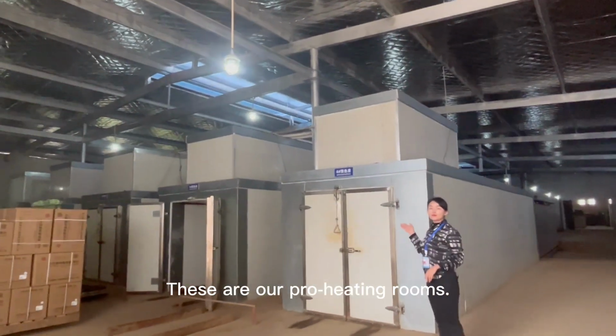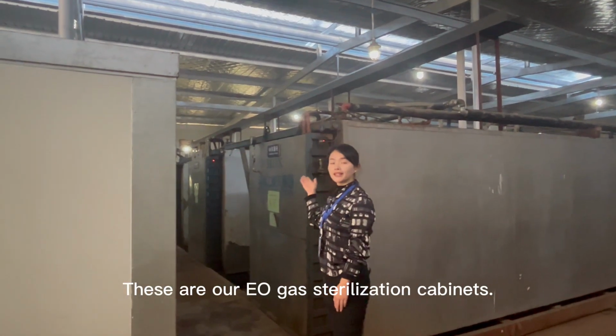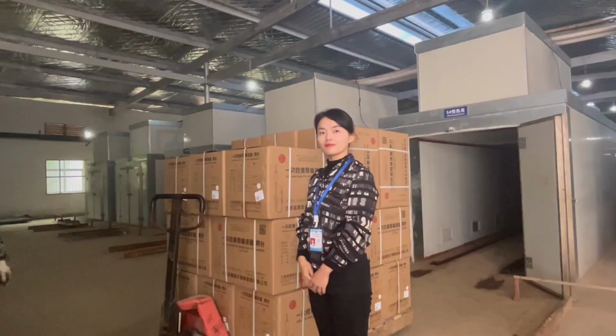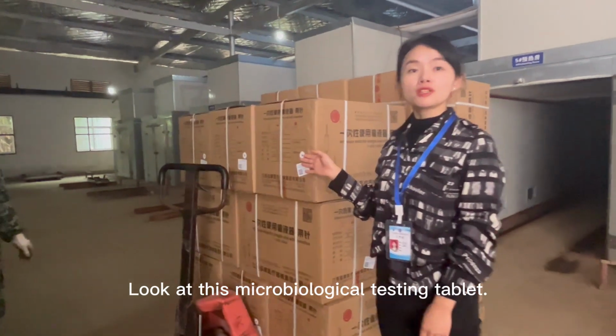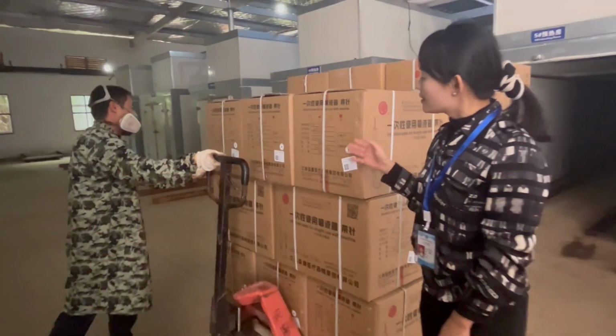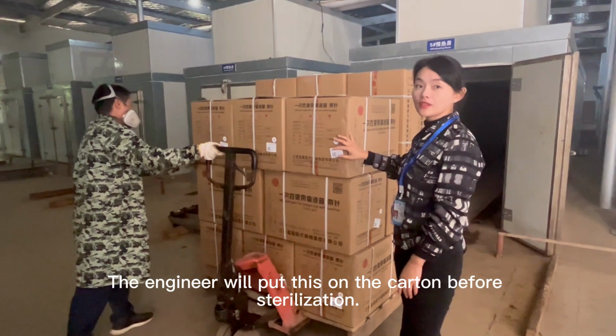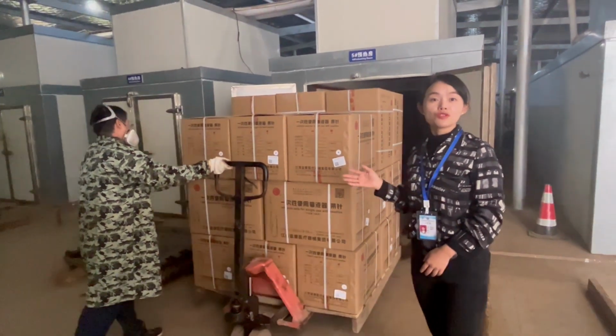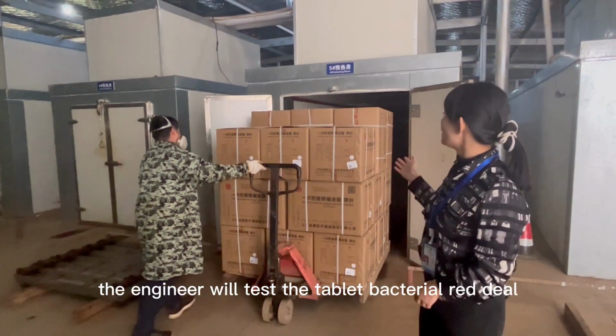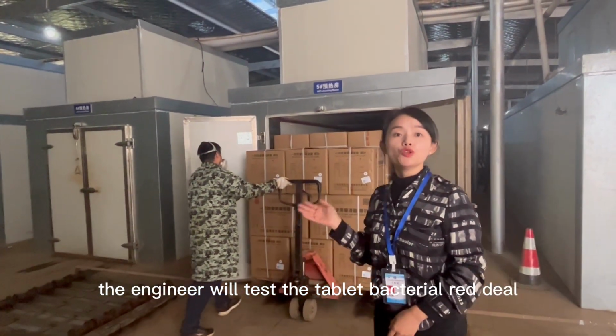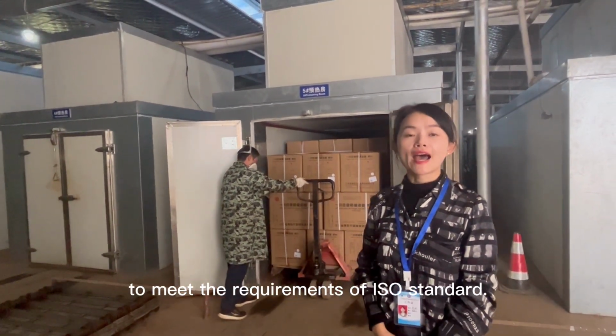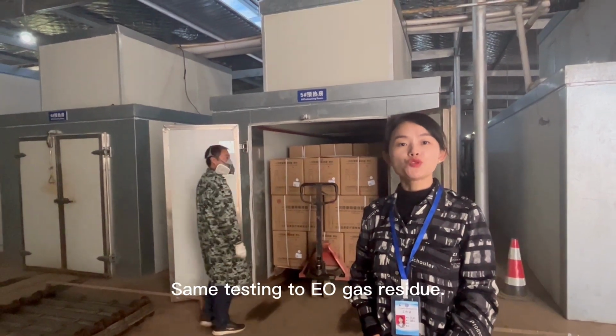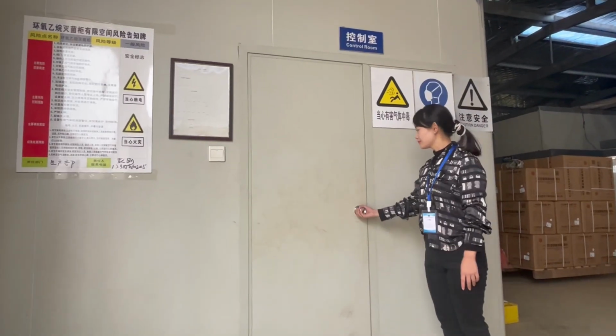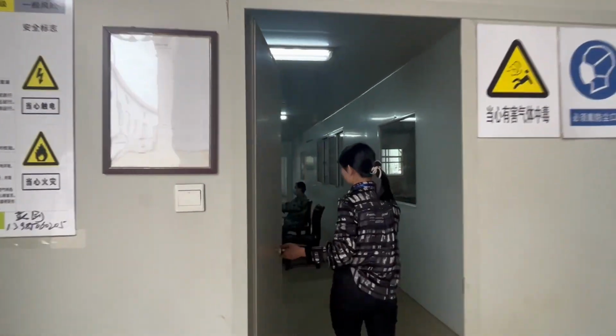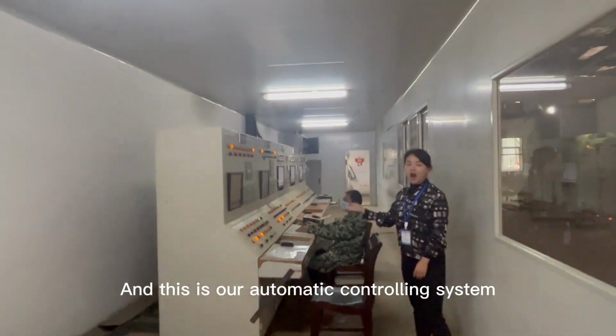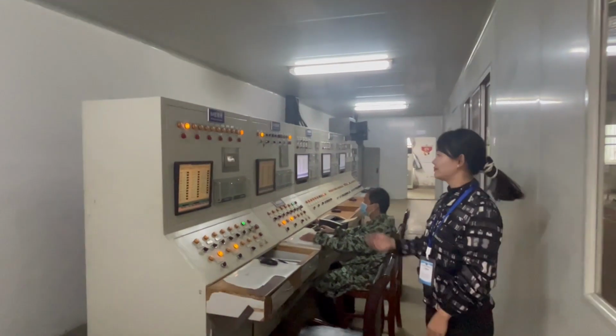These are our preheating room. These are our EO sterilization cabinets. Look at this microbiological testing tablet. The engineer would put this on the carton. After sterilization, the engineer will test the tablet for bacterial residue to meet the requirements of ISO standard. Same testing for EO residue. And these are our automatic controlling system.